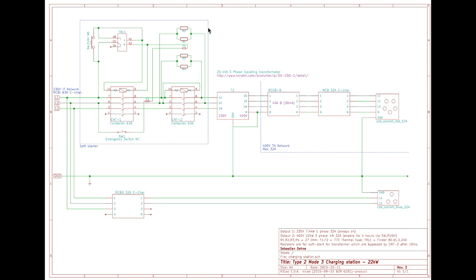And all the circuitry which is in front of the transformer is to control the transformer, switch it on and off, and to be able to soft-start it. So the way this works is that on the left side you have the three phases coming in, and as soon as this first contactor here is switched on, then current will start to flow towards the second contactor which is my soft starter. But this guy is still switched off, so what will happen is that electricity first starts to flow through my resistors up here and bypass the second contactor and then into transformer.